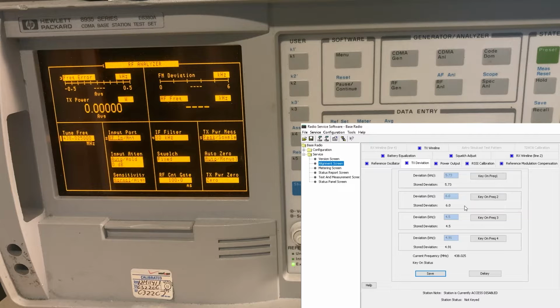5.73. And we'll do the same exact thing for the remaining 3. Key on. This one's 453.975, so we type in 453.975. We hear our tone again. And this time we're reading, we'll call it 6.14. Next frequency, 454.025, we're reading, we'll call it 4.60, yeah, 4.60, looks good to me. And finally, the last frequency, and we get 5.03, we'll call it. I don't think you have to be that precise. As long as you're within, I'd say, plus or minus 100 hertz, you're probably fine. So we've got all 4. We'll hit save again. It'll dekey, and that's all there is to it.